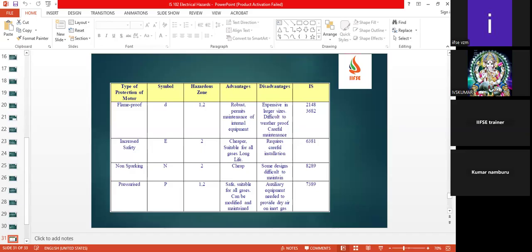Then non-sparking, which is also under zone 2, which is also cheap. Some design difficulties in maintenance, that is a disadvantage. Even we use non-sparking tools in production areas, where if you're working on any pipelines where there is a chance of presence of an atmosphere which will ignite if you're using such kind of tools or doing any hammering or any cutting, it will create a spark and lead to accidents.